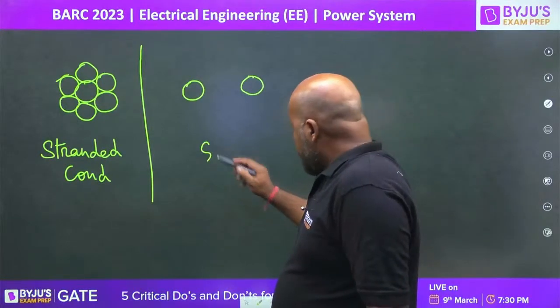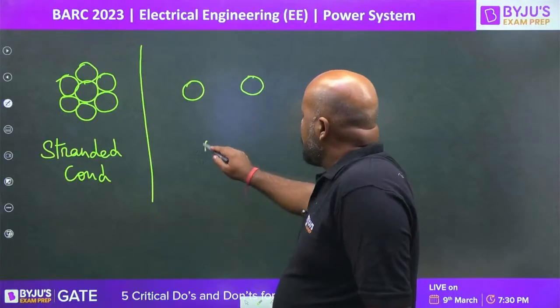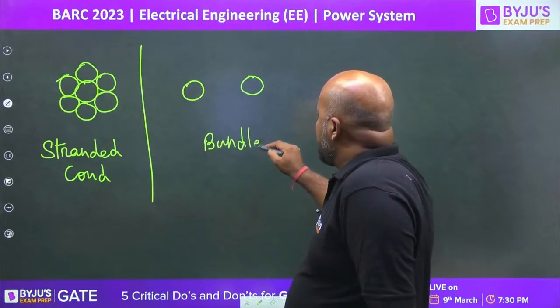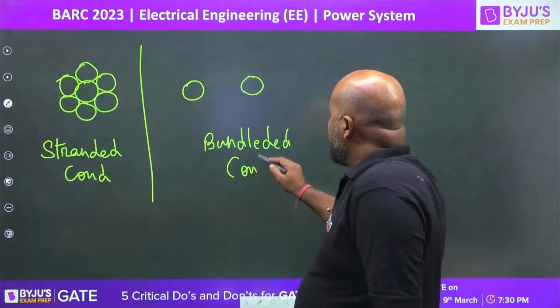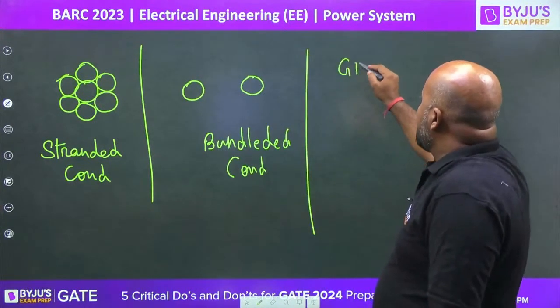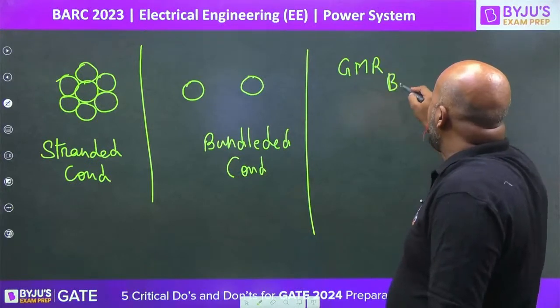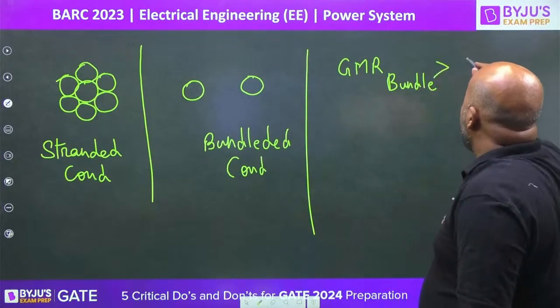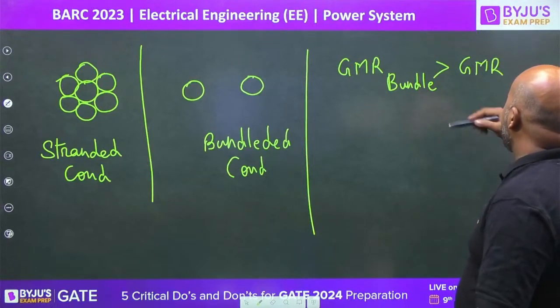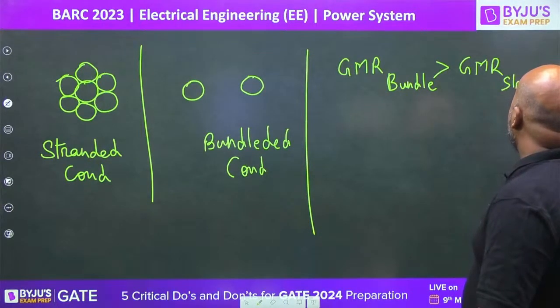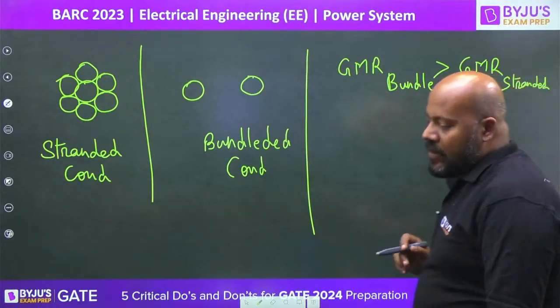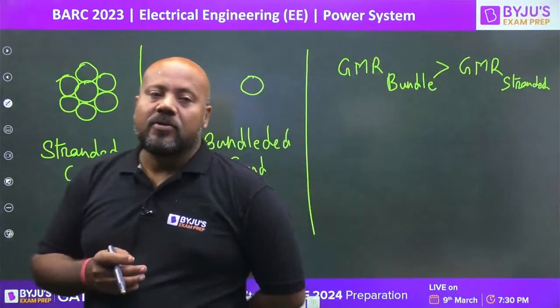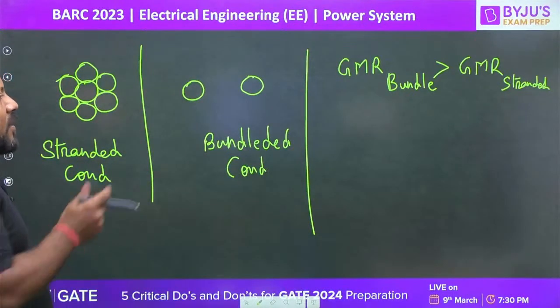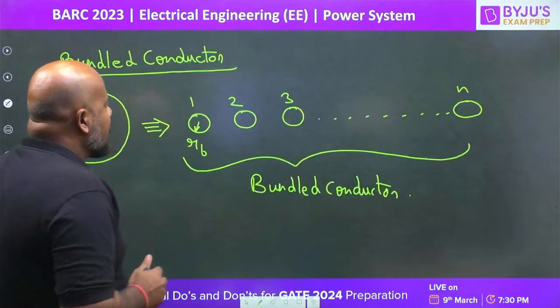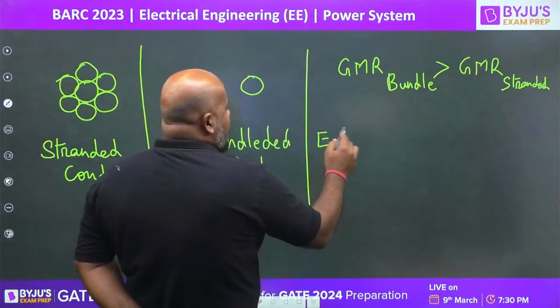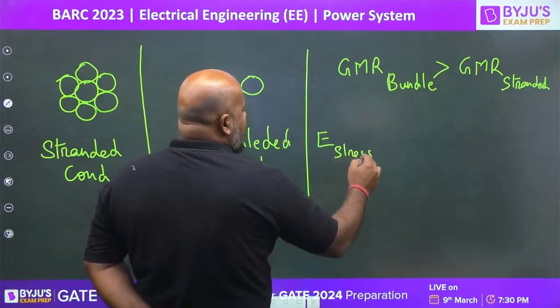Because of this reason, the GMR for a bundled conductor is going to be higher compared to a stranded conductor. So basically, by using bundled conductors, you are increasing the GMR. What happens if you increase the GMR? The electric field stress at the surface of the conductor...